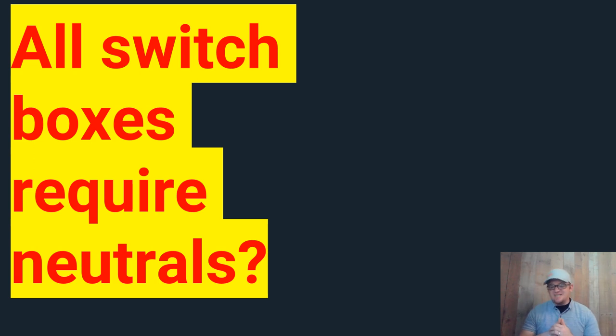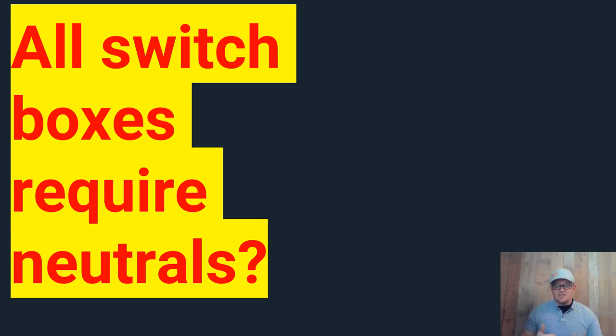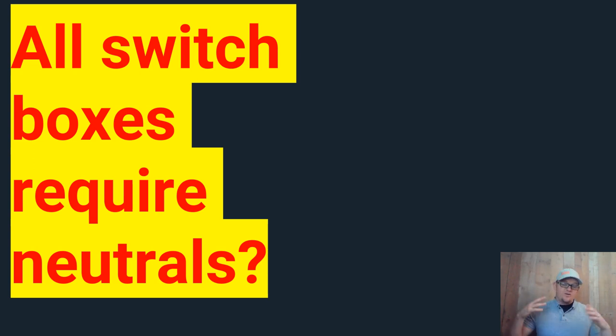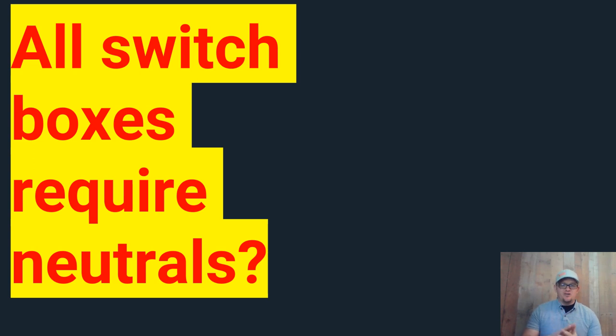So here's the score guys. The answer is no, you do not have to put a neutral inside of every box. Now, is it practical to? Yes. Should we probably do it? Yes. Are we required to by code? No. As long as you can hit any one of these five points, I gave you the most common ones that you're going to run into today. You can read the other ones. You'll find yourself in 404.2c.